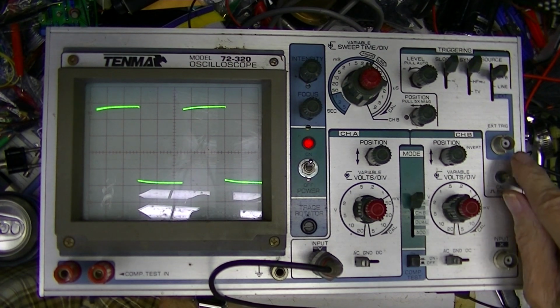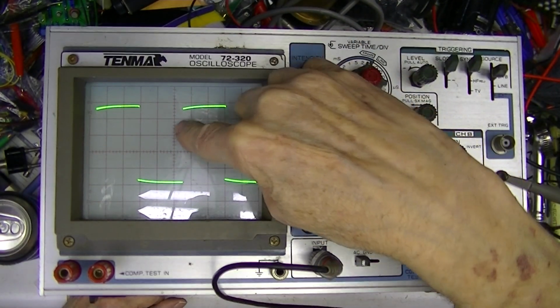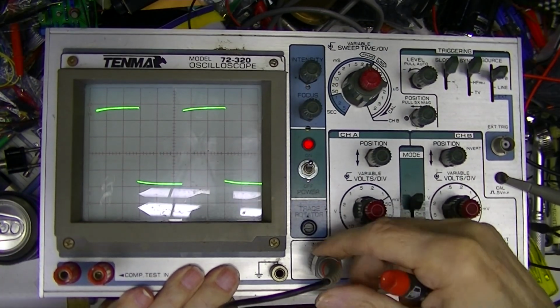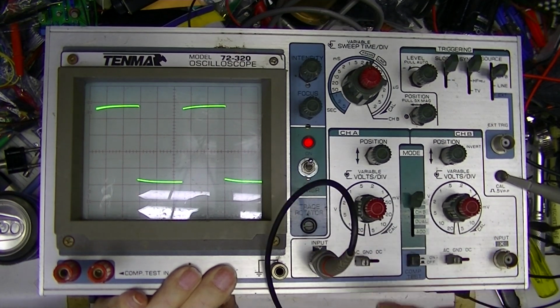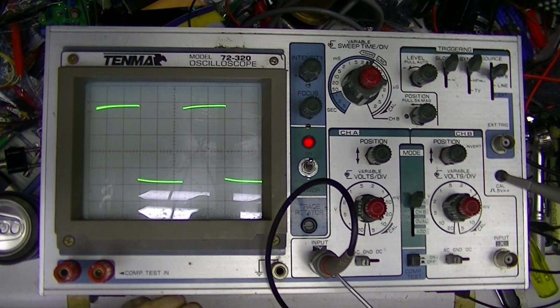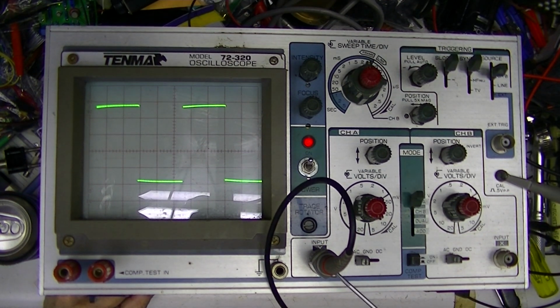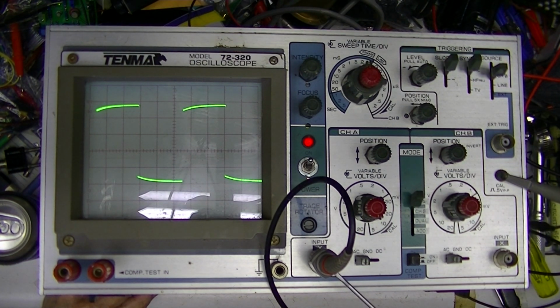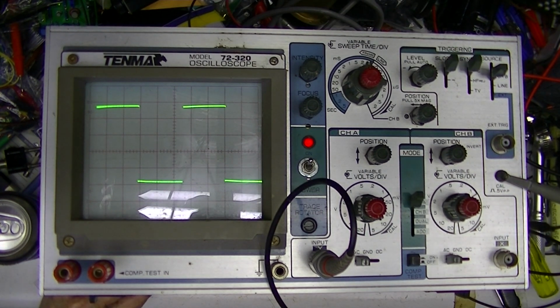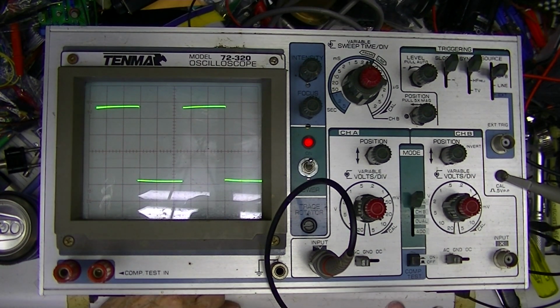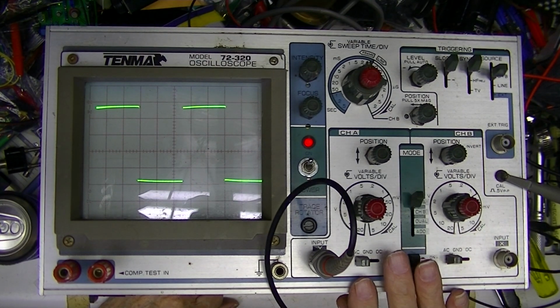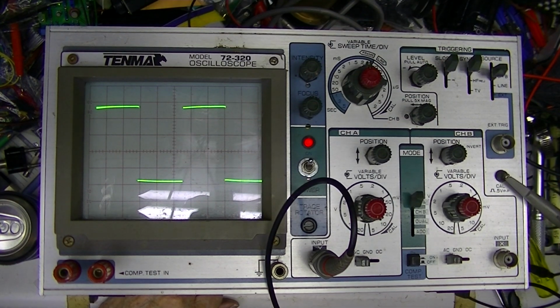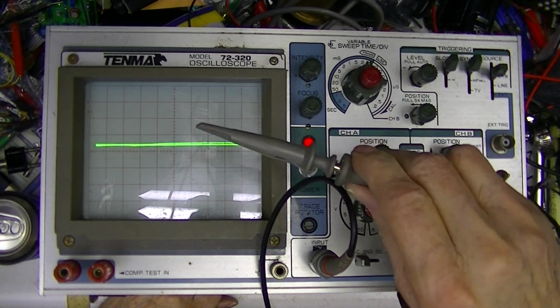Okay? This is supposed to be a square wave. That doesn't look very square. The little adjusting screw I talked about in here, let me adjust that screw a little bit. See what's happening? I'm bending the top and the bottom. What I'm trying to do is get this perfectly flat on top. That matches the probe to the oscilloscope. So if you are reading voltage and you are off by a factor of 10, check this switch.